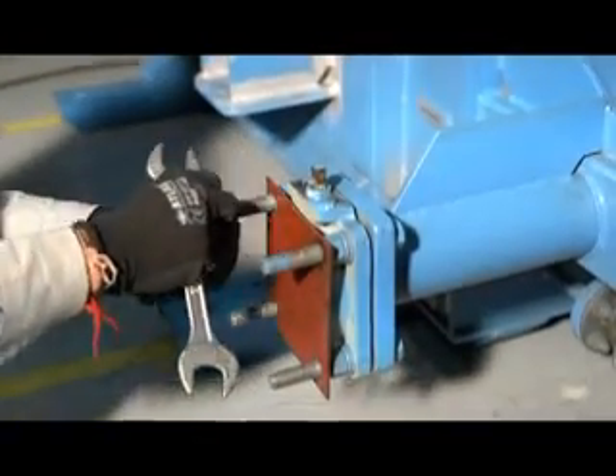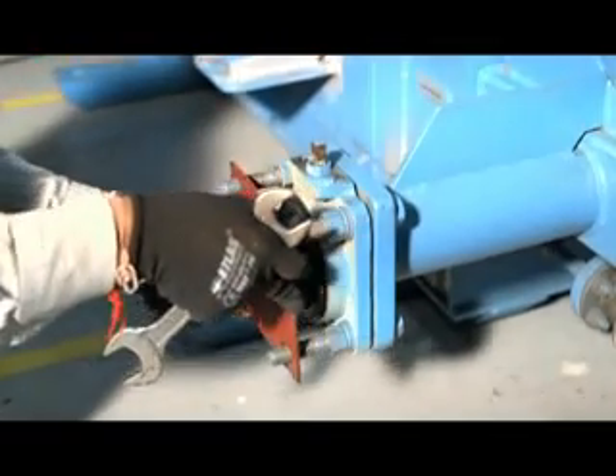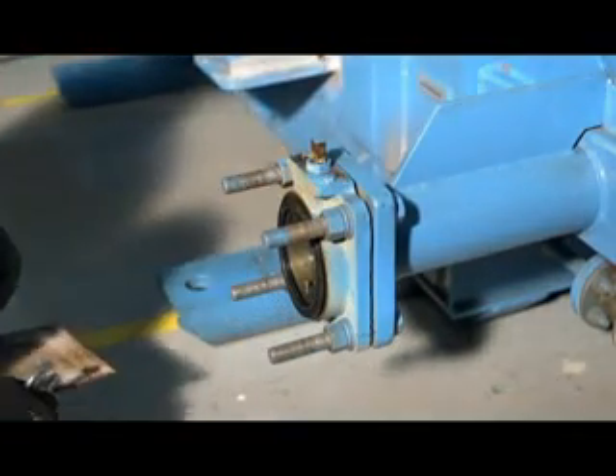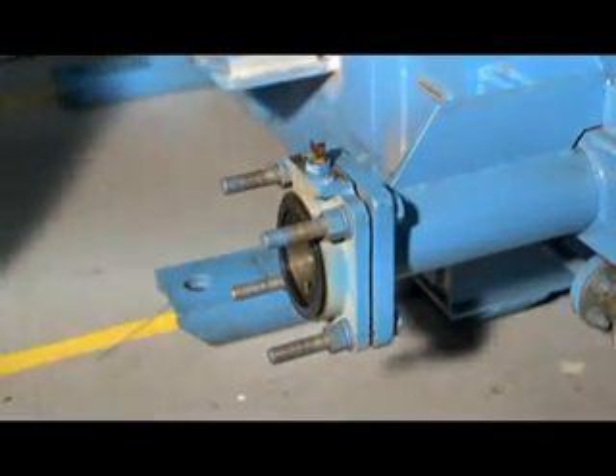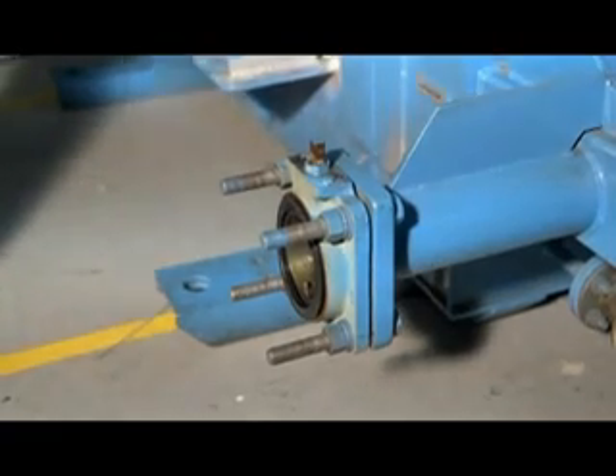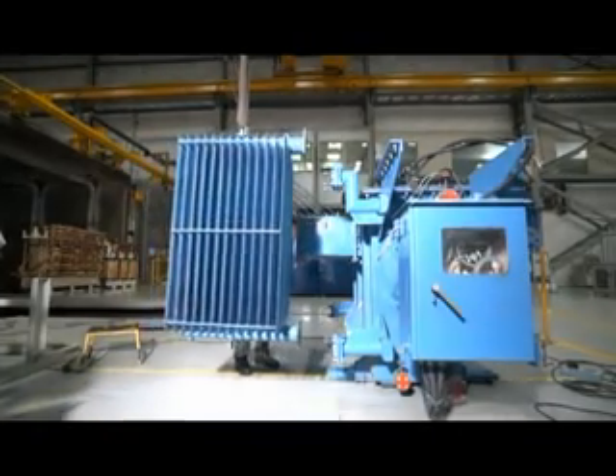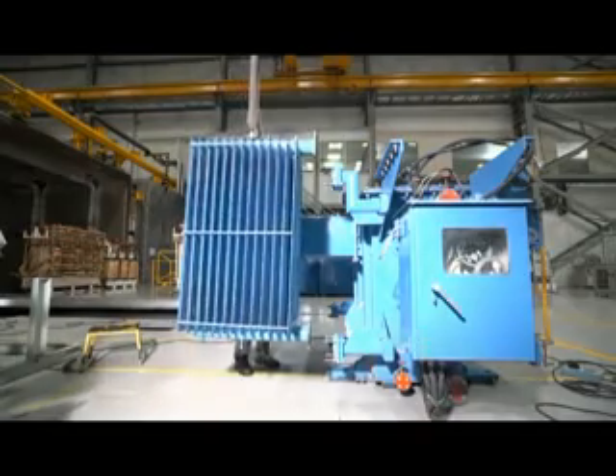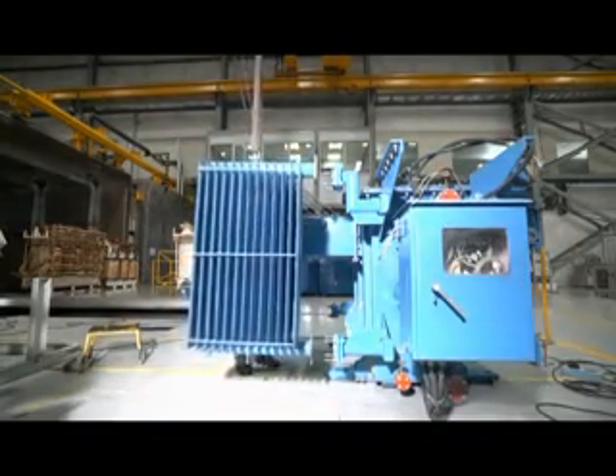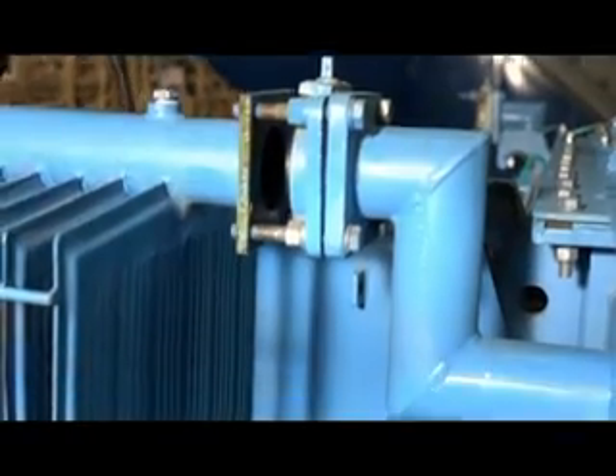The assembling should be started from one side and finished at the other side. Before assembling the unit, remove the blanking plates from the top and bottom radiator valves. While removing the blanking plates, if the gasket surface is damaged, it should be replaced by a new gasket. Then the radiator unit is lifted vertically and brought nearer to the respective main tank valves.